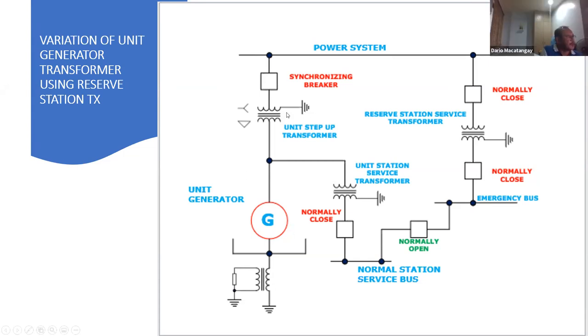Let's say you have a fault here, then you can still maintain power to the emergency system, okay? And actually you can still power all the loads needed to support this generator. Let's say this one trips. If this one trips, this one will open and this one will open, right? There's a fault here. This one will open, this one will open. However, this one will close, okay? So upon closure of this breaker, you're actually powering all the loads used to support the generator operation. So it's not going to be a bad thing, because you have less time to energize and prepare all the units for the restart.